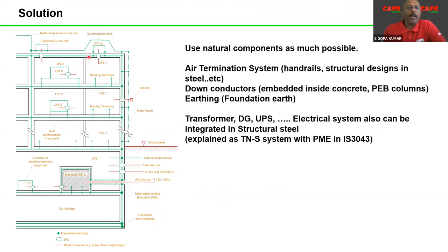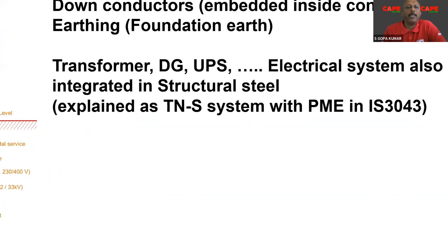So this particular use of natural components can also be used for applications such as transformer and DG. Our typical method is two earth electrodes for the transformer neutral, two for the transformer body, two for the DG, a separate earth electrode for the UPS, a separate one for the lift, and so on. Actually, the method we use for separate earthing of transformer, DG and UPS is, of course, a wrong method.